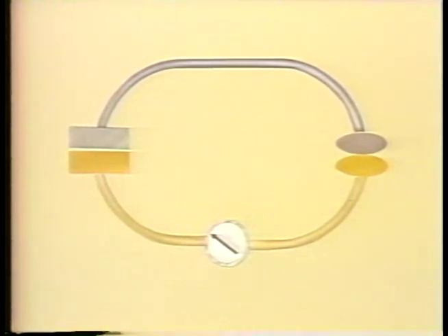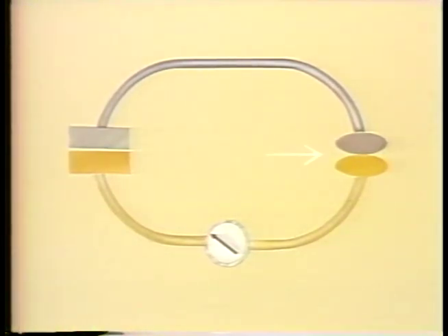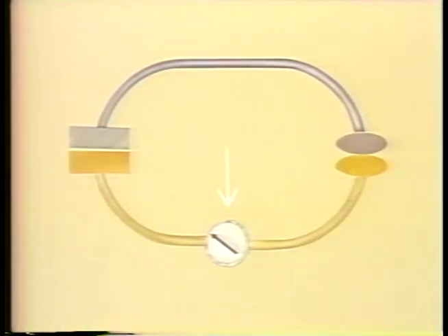We can see one application of this principle by looking at a simplified diagram of a thermocouple. A thermocouple consists of two wires made of dissimilar metals which are joined together. Where the two metals are joined is called the hot or measuring junction. The other end of the wires complete an electrical circuit at the cold or reference junction. When heat is applied to the measuring junction, one metal gives up electrons while the other accepts electrons, and a current flow is produced. The current flow is proportional to the temperature difference between the reference junction and the measuring junction.